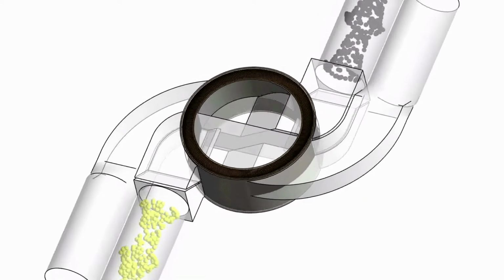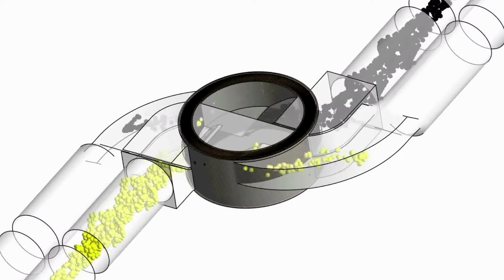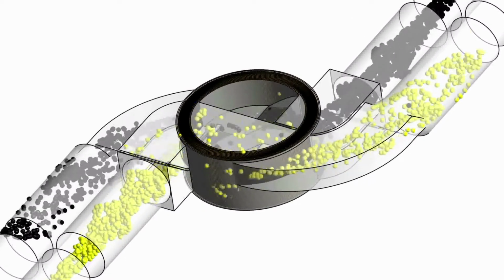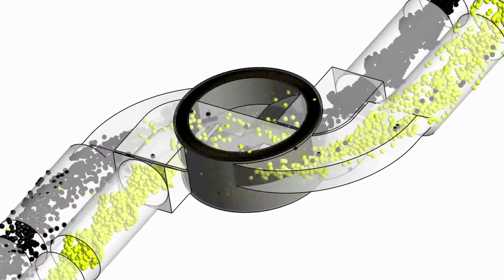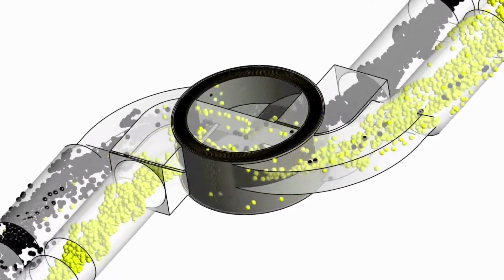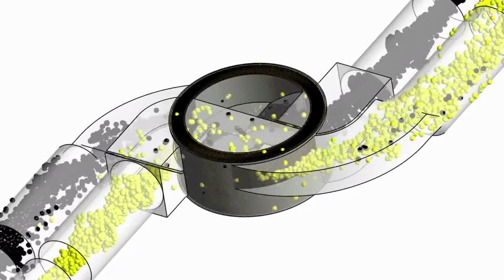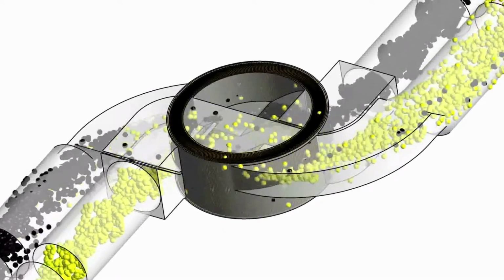Through this flow conduction, it's possible to realize a counterflow regime to achieve a highly efficient heat recovery, and in addition, occurring condensate can be recovered during the cold and dry season and no frost protection is required.